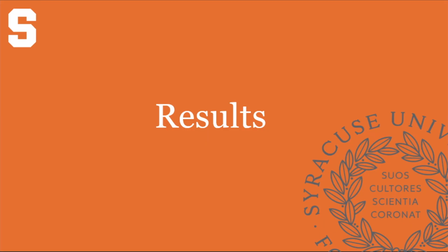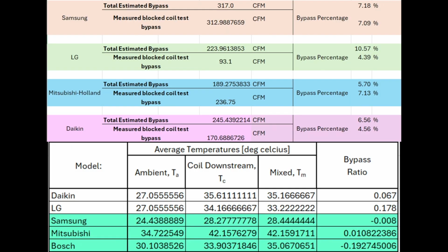As for the results of our tests, we can see that there are some discrepancies between the characterization calculations and the measured blocked coil tests. We can see that Samsung has very close bypass percentages between the two methods, and the Daikin has overall the lowest amount of bypass. Now drawing your attention to the temperature mixing methods, we can see the 3 heat pumps that are highlighted in green. These are unusable data. This is because sunlight that has shined on the probes affects the temperature reading.